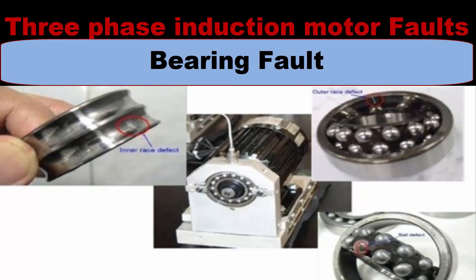Bearing fault: in three-phase induction motors, two sets of bearings are installed inside the motor housing for supporting the motor shaft. Their main purposes are to rotate the motor shaft freely and reduce friction. They consist of an outer and inner ring called races, and a set of rolling elements called balls. The balls are fixed on the inner and outer sides of the ring and reduce shaft friction, which can be further reduced by lubrication. If the balls or the outer or inner ring of the bearing are damaged, this bearing fault causes the motor to jam or become stuck. Motor bearing fault is shown in figure.